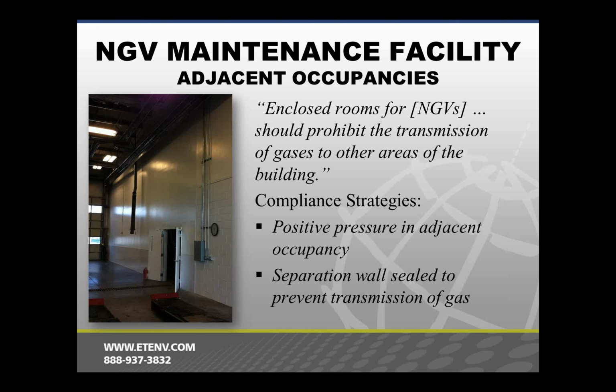Now, there's been differing opinions on whether that separation needs to be fire rated or not, and the approach that we've been taking and others have as well is that if there's indoor fueling involved, you definitely have to have a fire separation wall, or if there are other code requirements that are driving a fire separation wall, you need it. But if you're simply trying to keep a hazardous environment from natural gas vehicles from migrating to a different space, it's not a firewall. In fact, it's just mitigating measures to prevent that migration of gas.